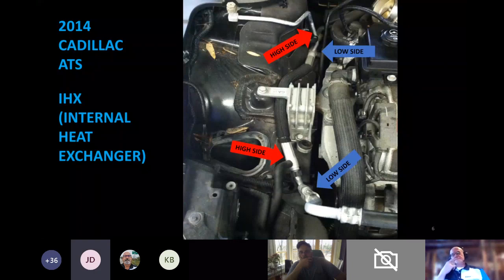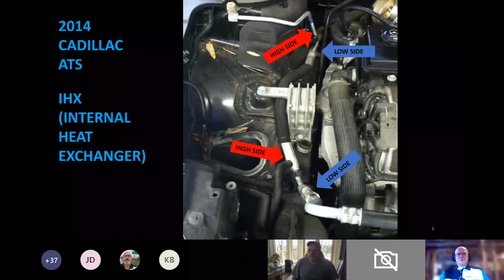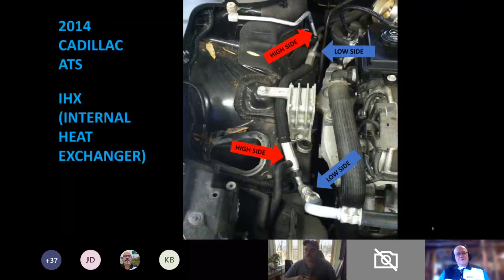Joe Hart was wondering if all 1234YF systems will be built on H block design, or are there any other orifice tube systems? The orifice tube is going away rapidly, and everyone is replacing it with the H block. I'm going to discuss the H block here in a moment, but it's my opinion that the orifice tube, which was good and was designed to replace the problem with the capillary tube and sensing bulb on the TXV, has some problems with a screen in there, of course, that everyone called Black Death when you had a compressor failure. And then other reasons for the accurate flow of refrigerant as a metering device. But it's my opinion and others that the orifice tube is being replaced pretty much with the H block. To answer Joe's question, I don't personally know of a 1234 system that uses an orifice tube. If there is one, I'm unaware of it.